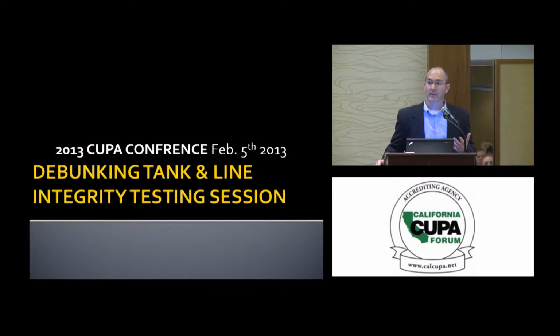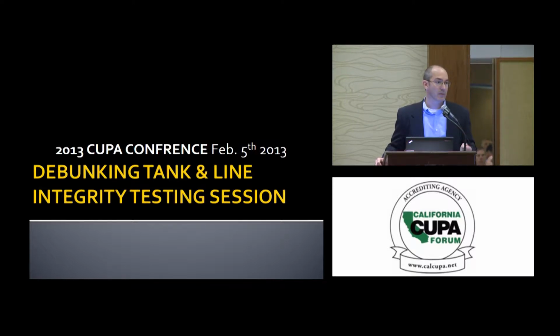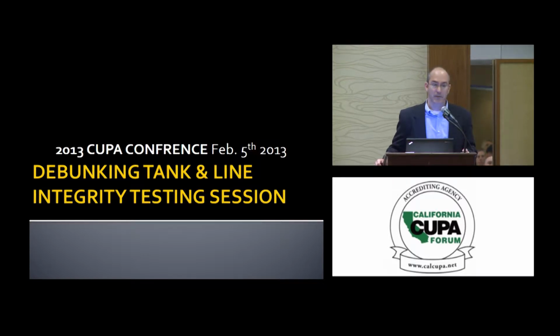But the EPA came up with a definition of a tightness test, which was a way to say, what size leak do we want to really be able to find in these tanks? They came up with 1/10 of a gallon per hour, which was what they considered kind of the best available technology, or kind of the smallest leak that could reasonably be discovered in a tank. It had to account for the effects that would impact that tank, things like the thermal expansion and contraction of the product, things like vapor pockets and tank deflection, and things like evaporation and condensation, and also the water that may exist in the soil down around the tank.